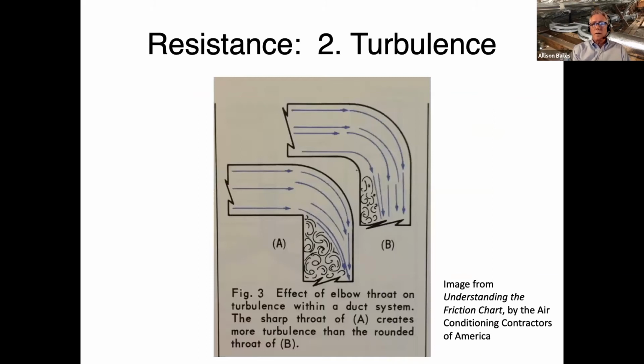The other factor that matters for resistance in the duct system is turbulence. So when you turn the air, when you split the air, when you put things into the airstream like dampers, you build up turbulence in the airflow, and that also slows down the air. So those are pressure drops, things that change the pressure.